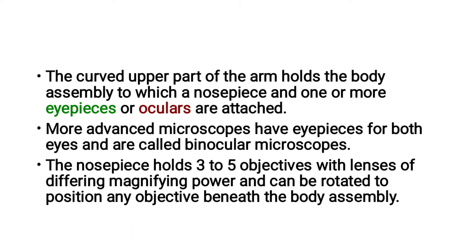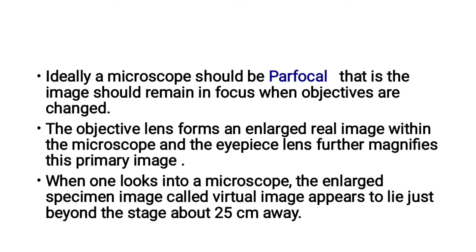The curved upper part of the arm holds the body assembly, to which a nose piece and one or more eyepieces, or ocular lenses, are attached. More advanced microscopes have eyepieces for both eyes and are called binocular microscopes. The nose piece holds three to five objectives with lenses of different magnifying power. It can be rotated to position any objective lens beneath the body assembly. Ideally, a microscope should be parfocal — that is, the image should remain in focus as objectives are changed.